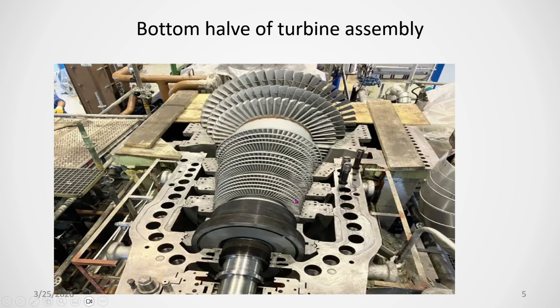As per the protocol, you again have to bring the rotor down, not the guide blade carrier down, and through the filler gauge you can measure the gap between the guide blade carrier blade and the rotor shaft, and the rotor blade to the guide blade carrier, so that equal clearances will be there throughout the blade and throughout the rotor. This is the way we do the centering of the rotor.